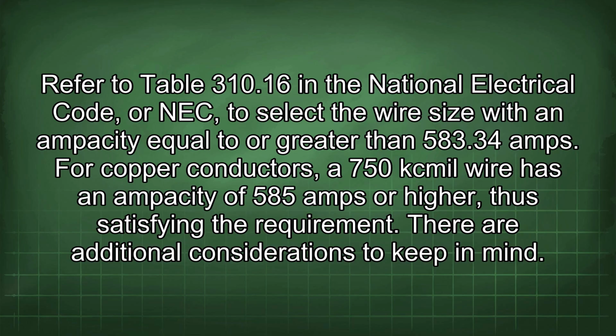Refer to Table 310.16 in the National Electrical Code, or NEC, to select the wire size with an ampacity equal to or greater than 583.34 amps. For copper conductors, a 750 kcmil wire has an ampacity of 585 amps or higher, thus satisfying the requirement. There are additional considerations to keep in mind.